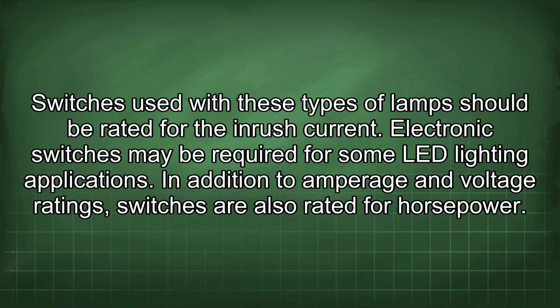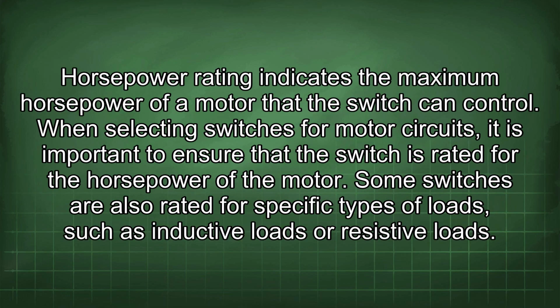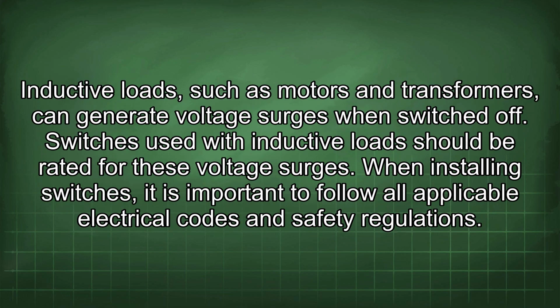In addition to amperage and voltage ratings, switches are also rated for horsepower. Horsepower rating indicates the maximum horsepower of a motor that the switch can control. When selecting switches for motor circuits, it is important to ensure that the switch is rated for the horsepower of the motor. Some switches are also rated for specific types of loads, such as inductive loads or resistive loads. Inductive loads, such as motors and transformers, can generate voltage surges when switched off. Switches used with inductive loads should be rated for these voltage surges.